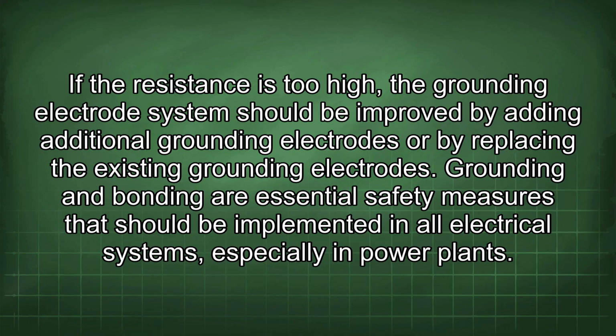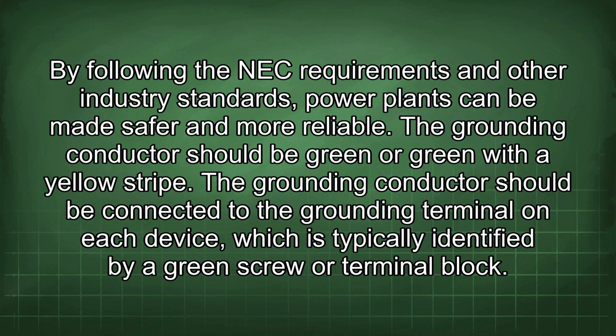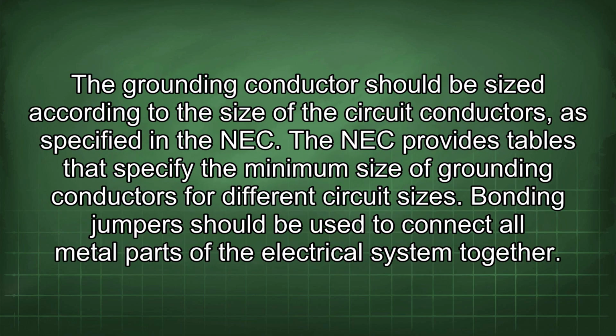Grounding and bonding are essential safety measures that should be implemented in all electrical systems, especially in power plants. By following the NEC requirements and other industry standards, power plants can be made safer and more reliable. The grounding conductor should be green or green with a yellow stripe. The grounding conductor should be connected to the grounding terminal on each device, which is typically identified by a green screw or terminal block. The grounding conductor should be sized according to the size of the circuit conductors, as specified in the NEC. The NEC provides tables that specify the minimum size of grounding conductors for different circuit sizes.